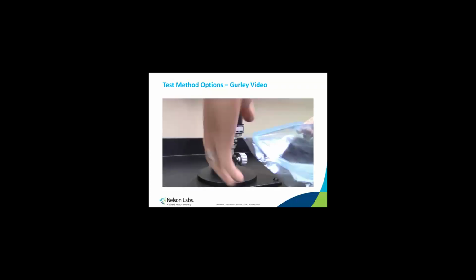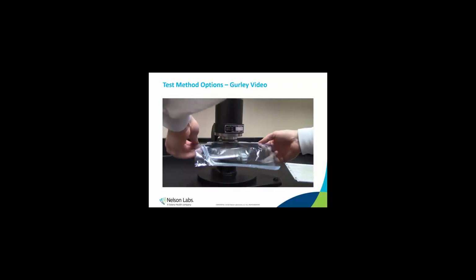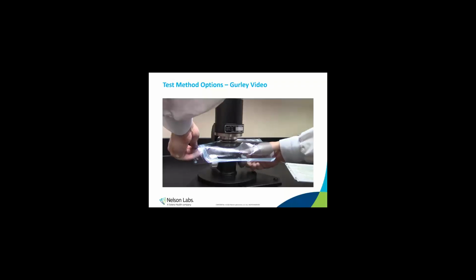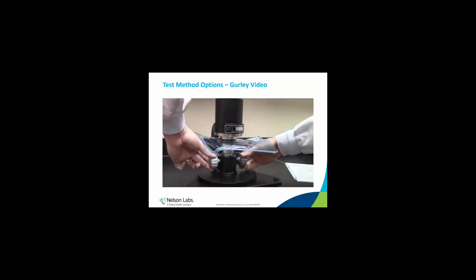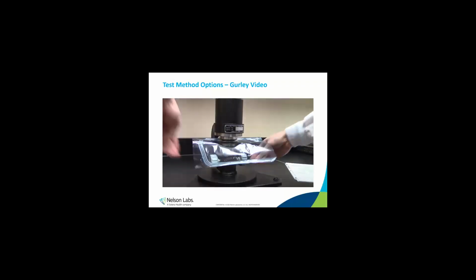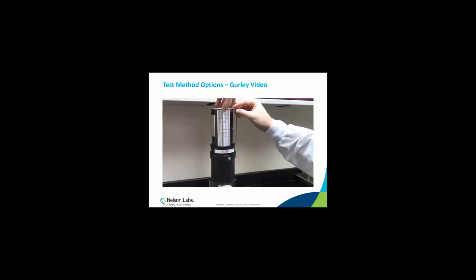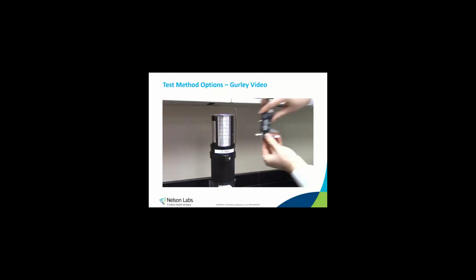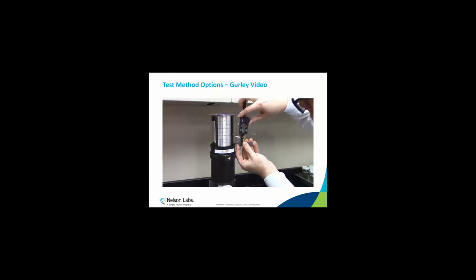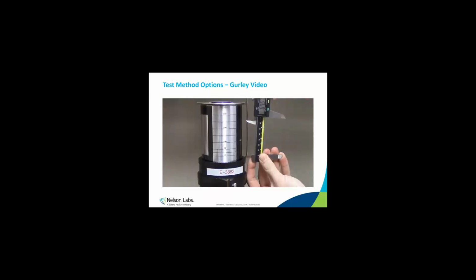Now let's look at the Gurley. This is a very simple and straightforward test, and it's for non-porous materials. We're going to take this material, we're going to put it in the tester and clamp it. And then we're going to release this cylinder and measure the distance. Now, if this were a porous material, that cylinder would continue to drop until it reached the bottom. We're going to measure this distance again after an hour.